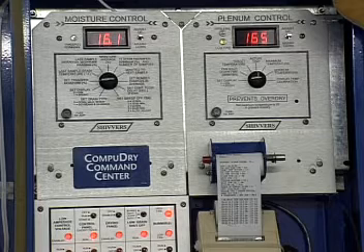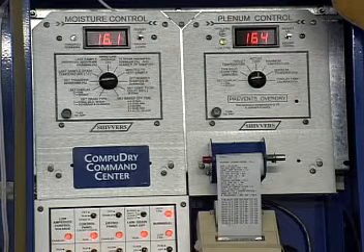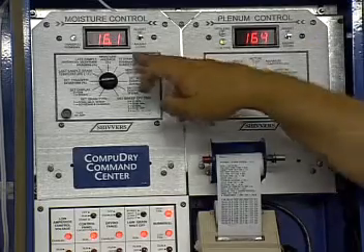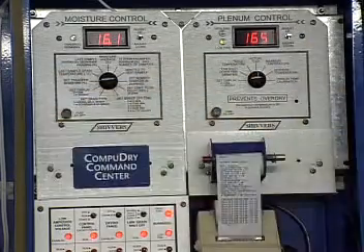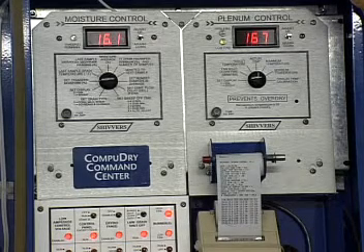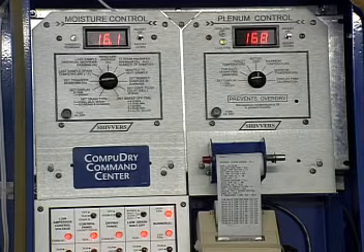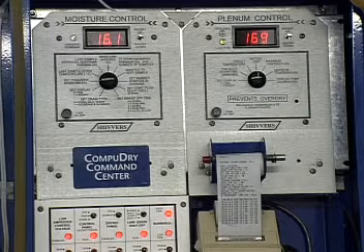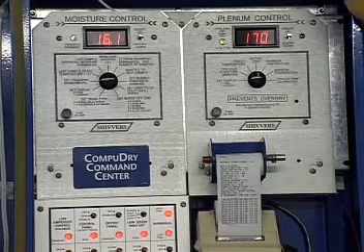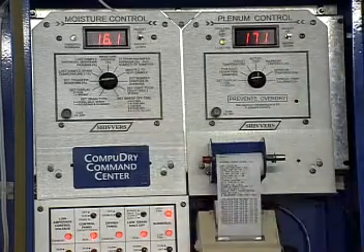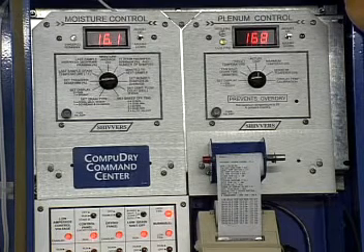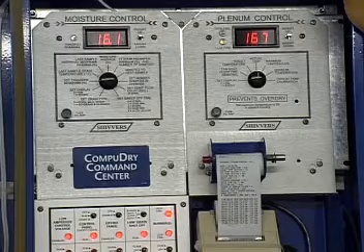In the instruction book, the operating instructions tell you that when you calibrate it the first time, you do exactly as we said. If you forget how to do it, it's listed right here on the side. The second time you calibrate it, maybe 2-3 days later, you check it again and say, I'm still a half point off. At that time, only go half of it. Go 2 to 3/10 of a point rather than a half point, because you don't want to go too far one way and then back the other way. Remember what we said at the beginning: set it, calibrate it, and forget it.